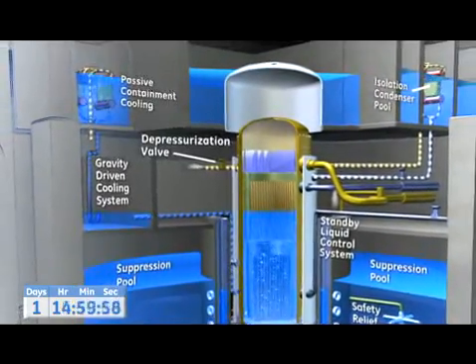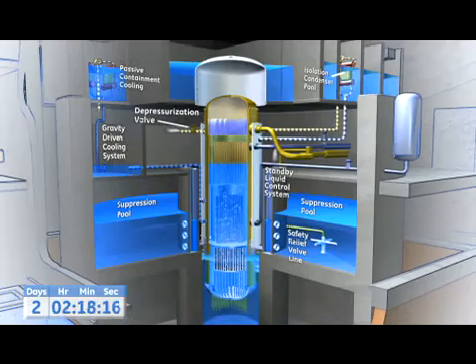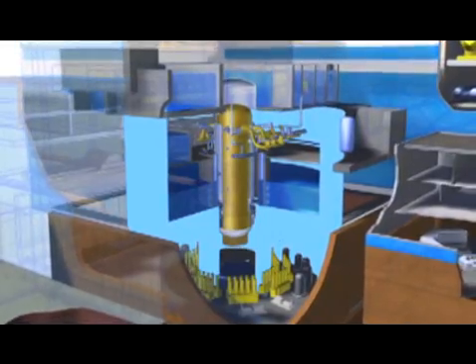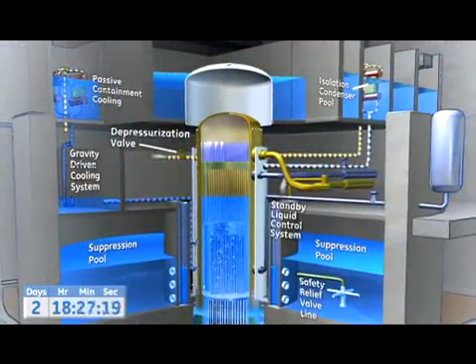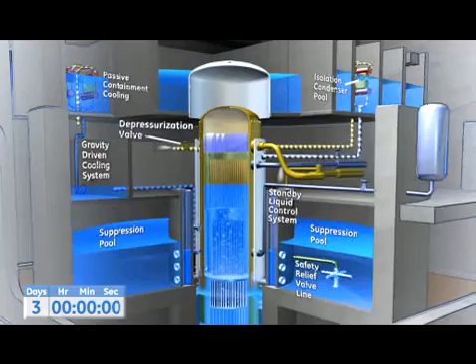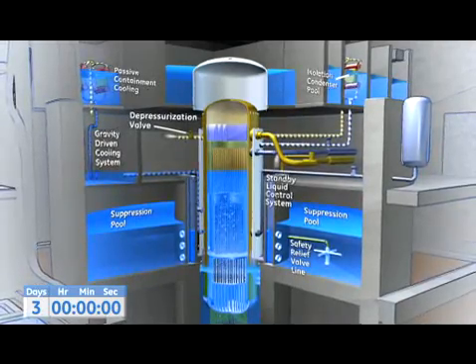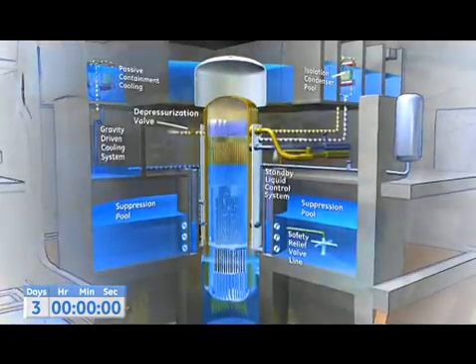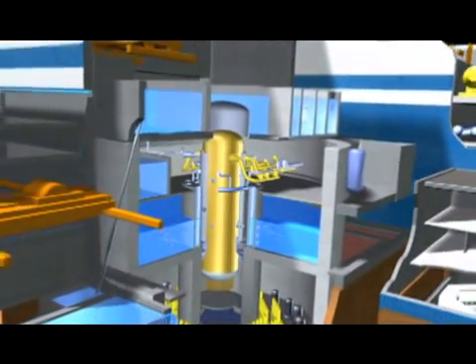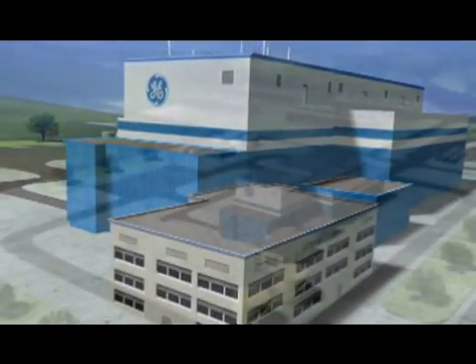Because the core has remained cooled through the sequence, the nuclear fuel does not heat up and the fuel tubes remain intact. If any radioactivity is released from the core, the containment building prevents its release into the environment. The ESBWR passive safety systems automatically keep the reactor core consistently cooled for 72 hours, unlike any operating nuclear plant. The pools are sized to remove heat from the core for three days, after which the upper pool will be refilled. In summary, accident events like pipe breaks can be accommodated by the ESBWR passive safety systems without any reliance on the AC power grid or even emergency generators for three days with no core heat up.